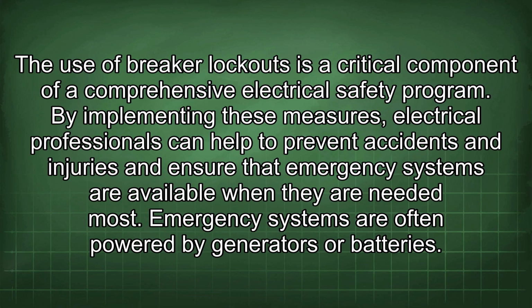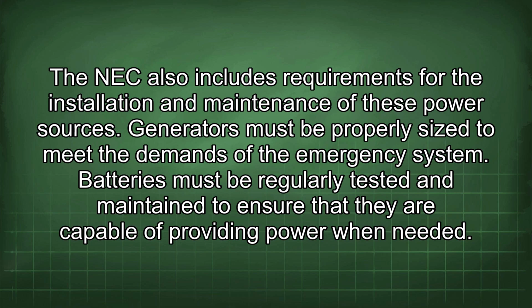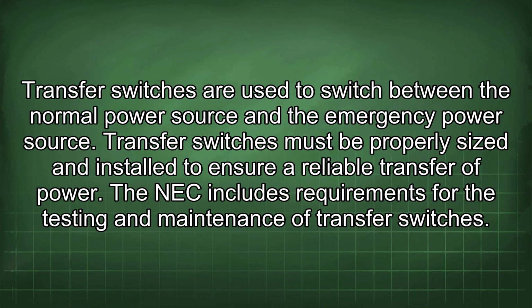Emergency systems are often powered by generators or batteries. The NEC also includes requirements for the installation and maintenance of these power sources. Generators must be properly sized to meet the demands of the emergency system. Batteries must be regularly tested and maintained to ensure that they are capable of providing power when needed. Transfer switches are used to switch between the normal power source and the emergency power source. Transfer switches must be properly sized and installed to ensure a reliable transfer of power. The NEC includes requirements for the testing and maintenance of transfer switches.